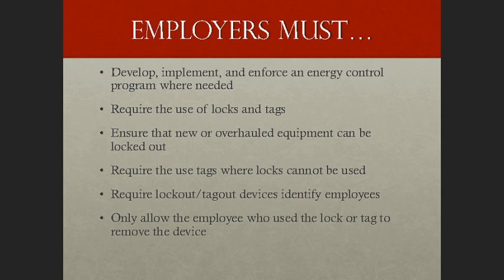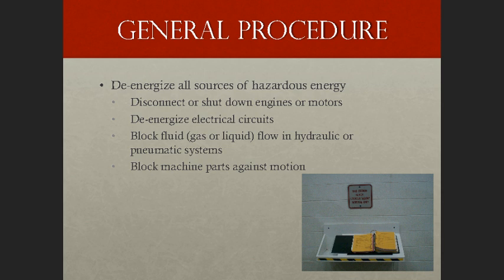Finally, employers must only allow the employee who applied the lock or tag to remove the device, though there are special cases where this isn't always possible. The first step in the general Lockout Tagout procedure is to de-energize all sources of hazardous energy — that means disconnecting or shutting down engines or motors, de-energizing electrical circuits, blocking fluid flow in hydraulic or pneumatic systems, and blocking machine parts against motion.